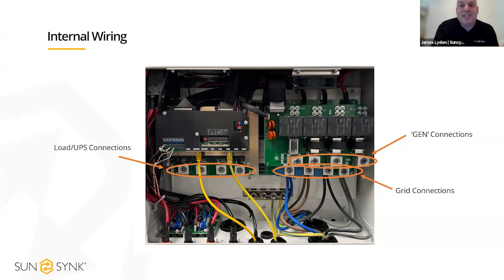There are 2 ways of AC coupling with our kit. If it is an existing grid side system, you can essentially chop the AC from the grid side inverter and connect it straight into us. Or you can leave that grid side connected back to the board, and with our CTs we'll see when that's exporting, and it will then divert it to the batteries.